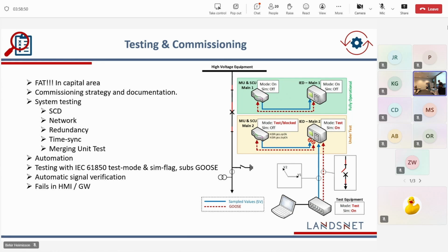Same with what we have defined. We have defined, for example, gooses from protection IEDs which have no subscribers. They were just including kind of every protection element in the IEDs, so we can bring in our test sets and subscribe to those gooses for testing purposes to have all the details, not only listening to trip and start contacts.